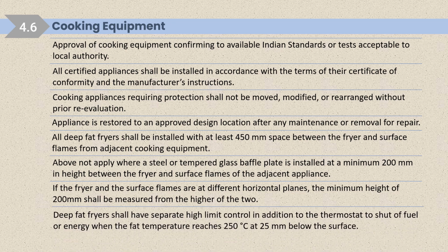Deep fat fryers shall have a separate high limit control in addition to the thermostat. Most deep fat fryers come with an inbuilt thermostat. Here we are talking about the high limit controls which should also be in place. When the fat temperature reaches 250 degrees centigrade at 25 mm below the surface, it should get shut off. So how do we measure the temperature? 250 degrees centigrade, 25 mm below the surface of the oil.